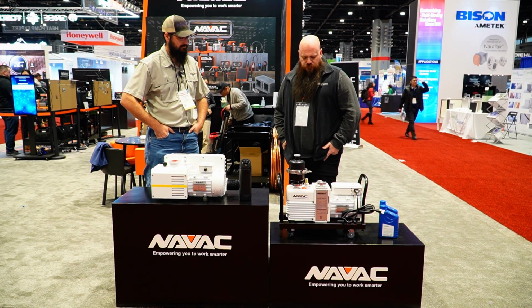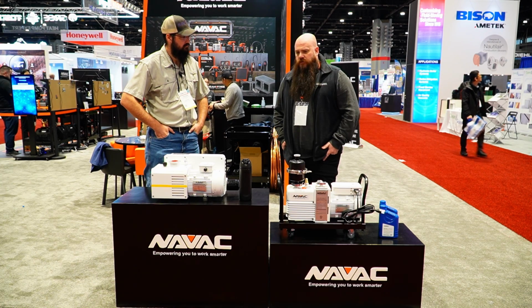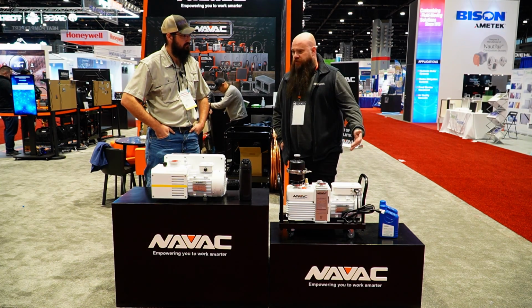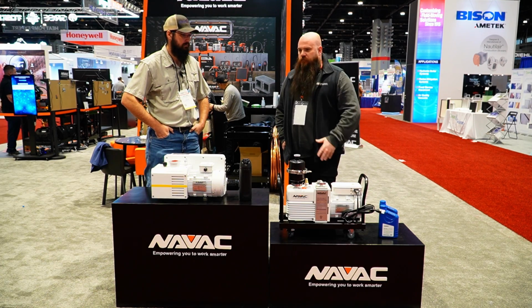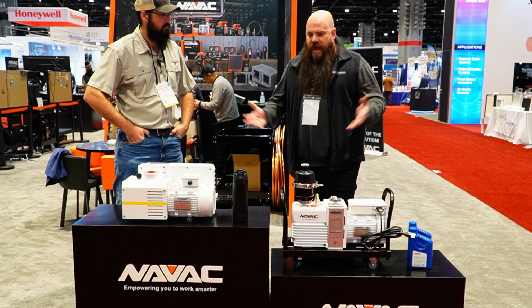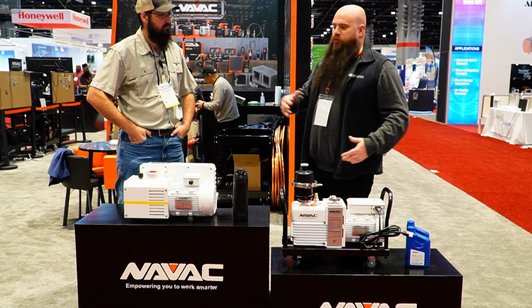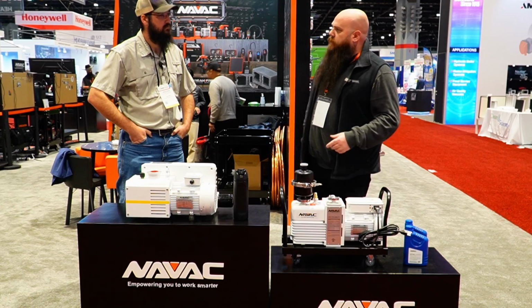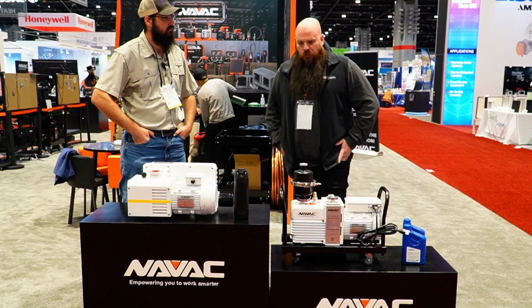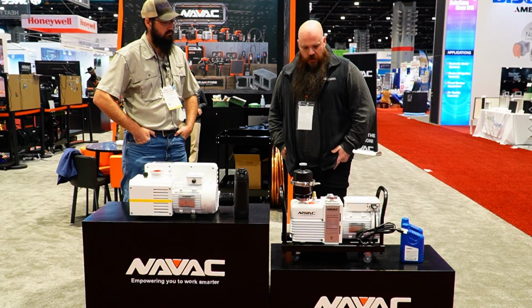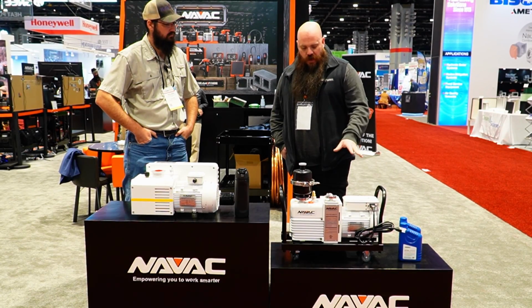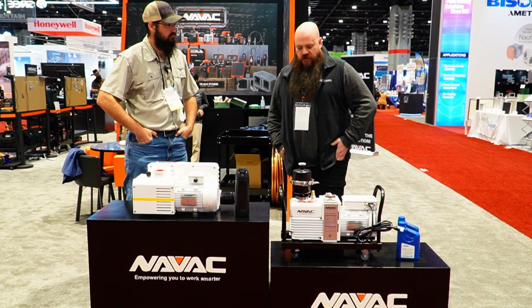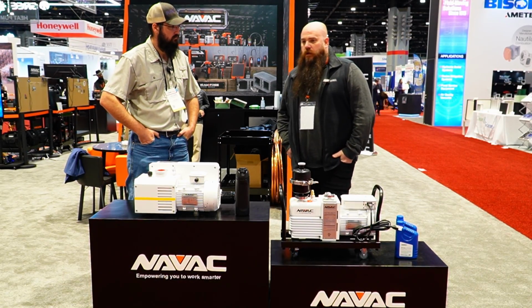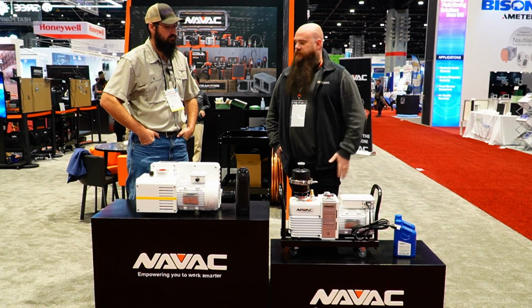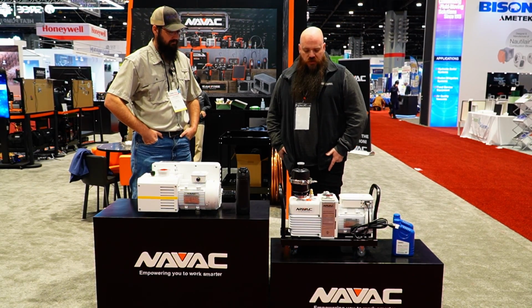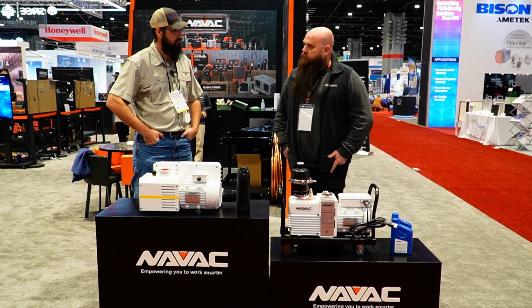This pump has been designed for applications outside of HVAC initially. It's used for freeze drying processes, other types of flash freezing operations with produce and things that I don't even know how to explain - frankly, it's out of my lane. But the point is, the build and tolerances in this pump are done in such a way that it's meant to run 24/7, for 6 months at a time at times. So that's where this really comes into play as an advantage for your chiller guys.